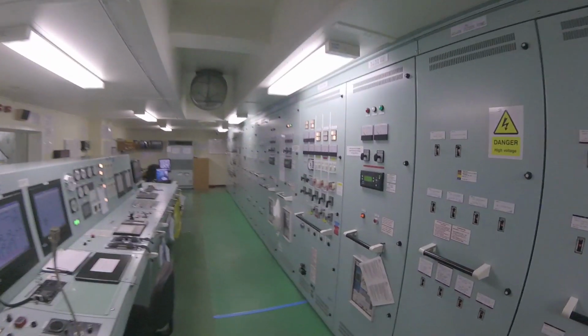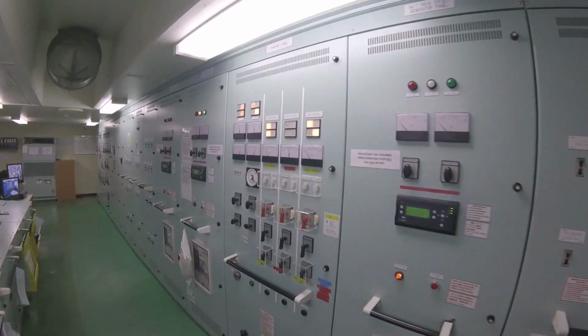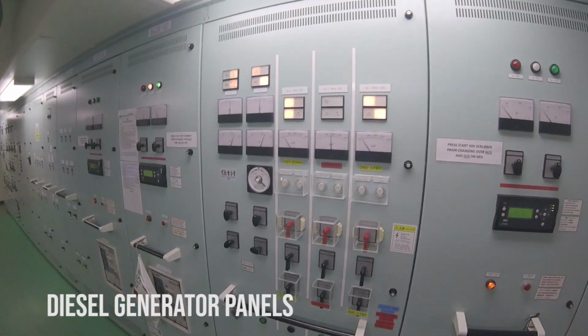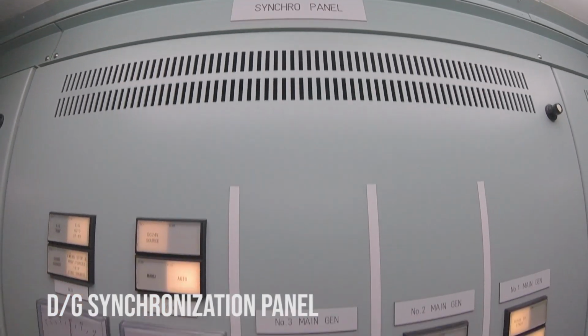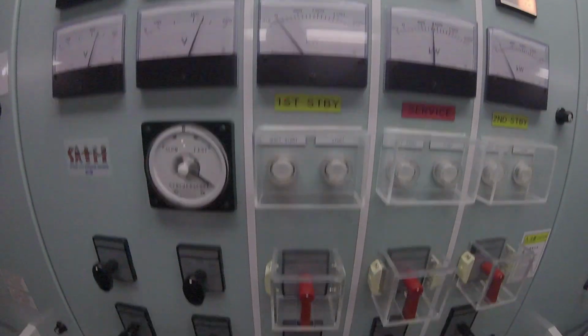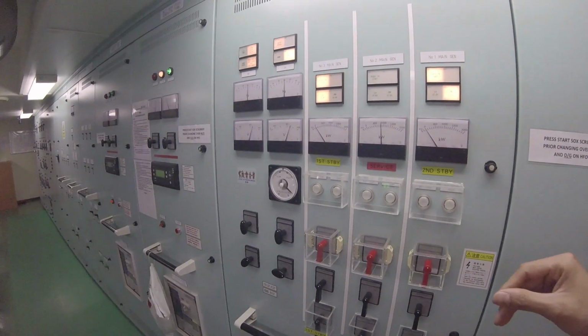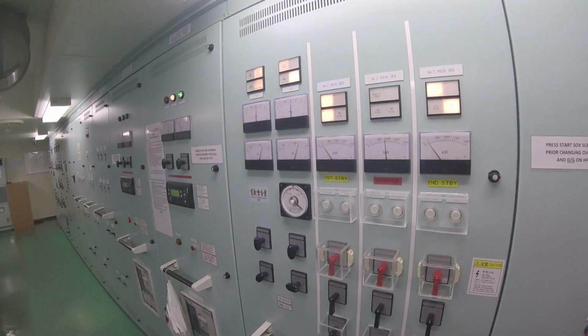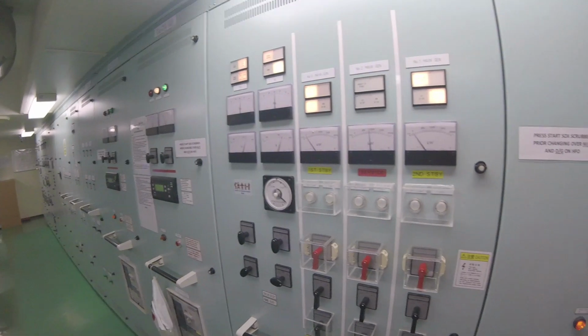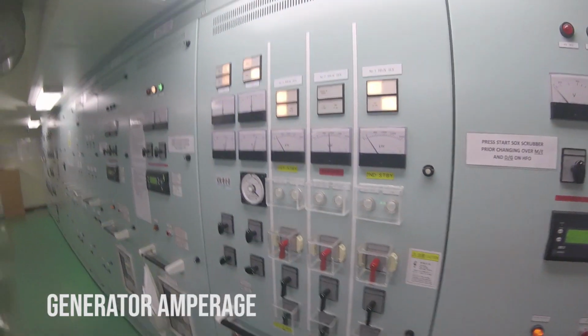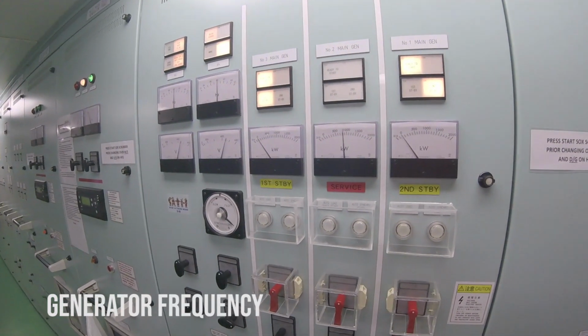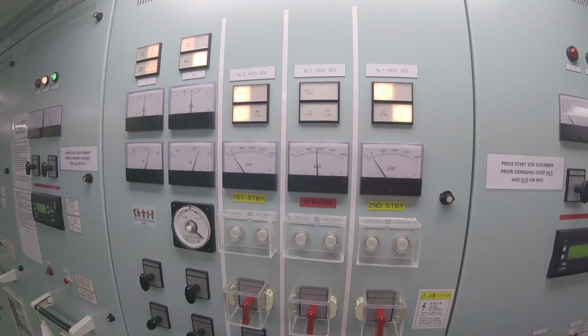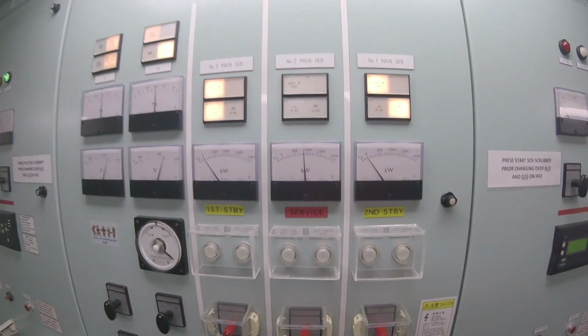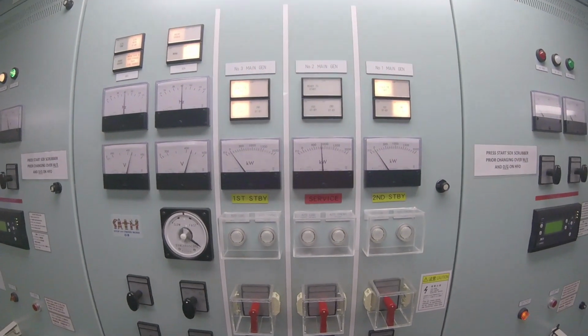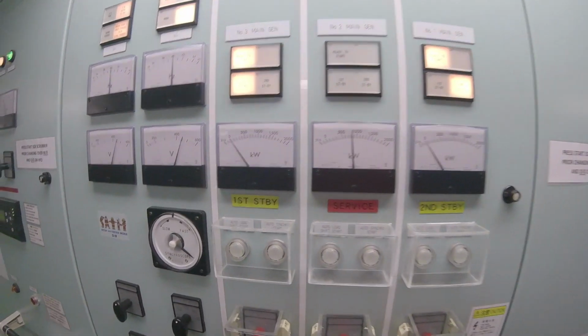Also fitted on the main switchboard are the generator panels and the generator synchronization panel. In these panels we can monitor some of the parameters of the generator. We can start and stop it remotely, and we can synchronize it and put it on parallel, either automatically or manually.